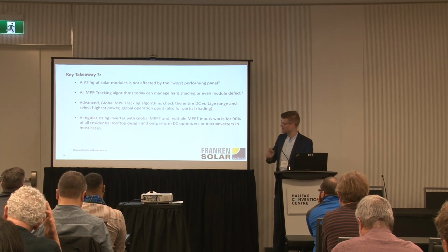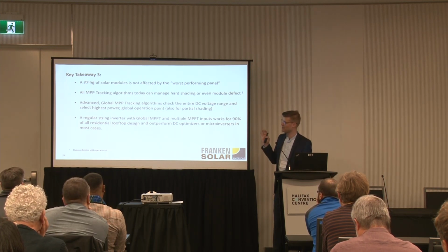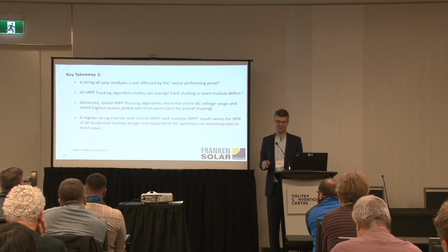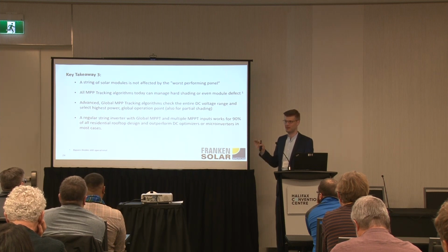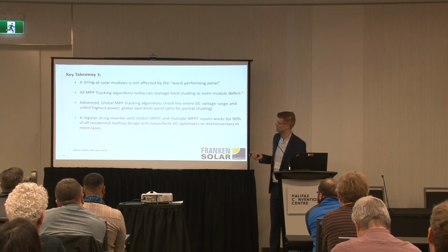A few key takeaways. The main message: a string of solar panels is not affected by the worst performing panel. It has never been true since the introduction of bypassing diodes. The thing that is affected is mainly the affected panel. The rest can operate with a normal string inverter.